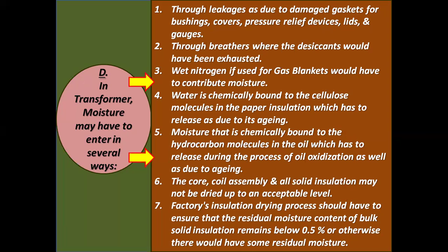Number four, water is chemically bound to the cellulose molecules in the paper insulation, which is released due to aging or high temperature. Number five, moisture is chemically bound to the hydrocarbon molecules in the oil, which is released during the process of oil oxidation as well as due to aging. Number six, the core, coil assembly and all solid insulation may not be dried to an acceptable level during manufacturing or after maintenance.